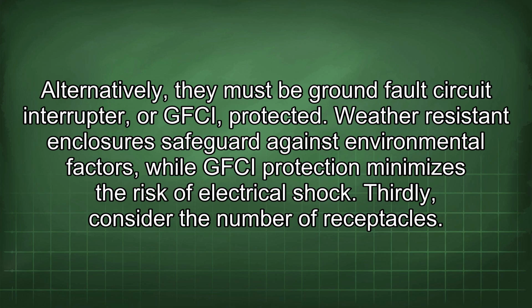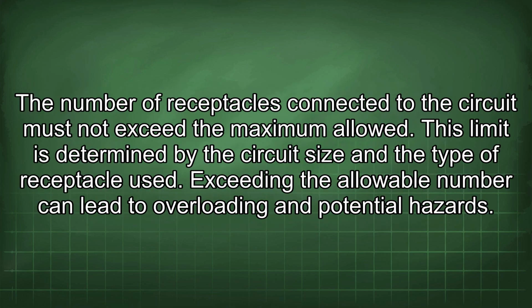Thirdly, consider the number of receptacles. The number of receptacles connected to the circuit must not exceed the maximum allowed. This limit is determined by the circuit size and the type of receptacle used. Exceeding the allowable number can lead to overloading and potential hazards.